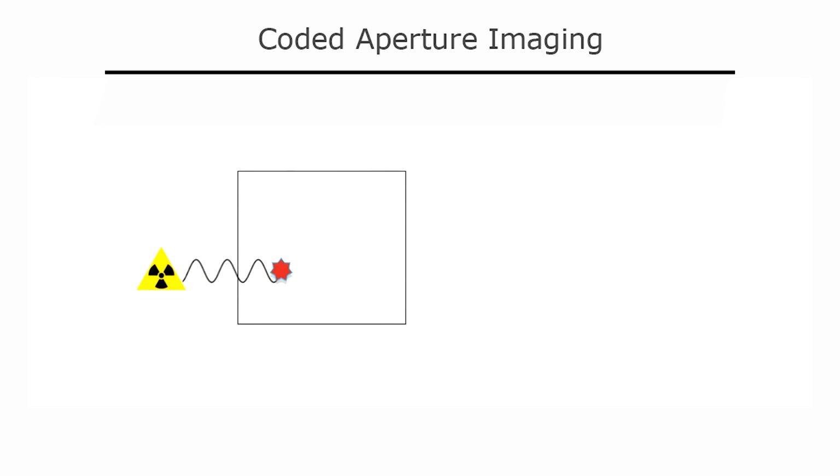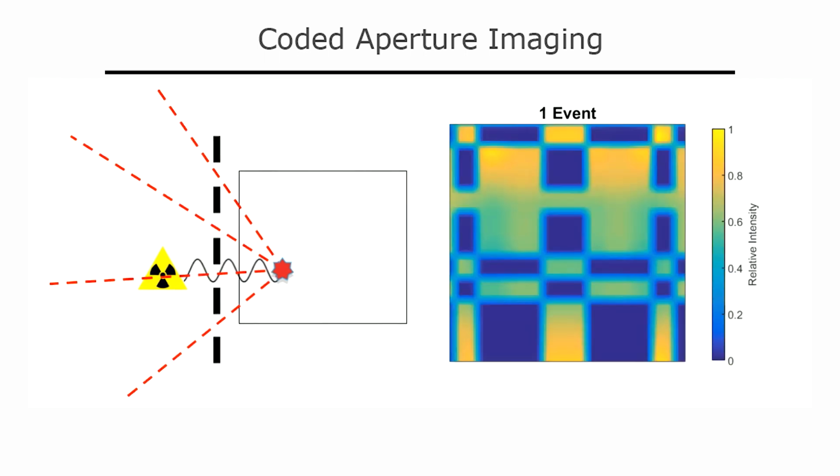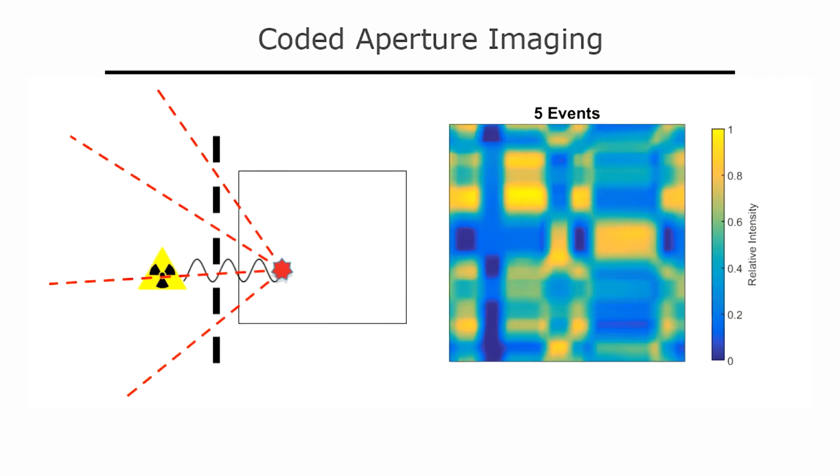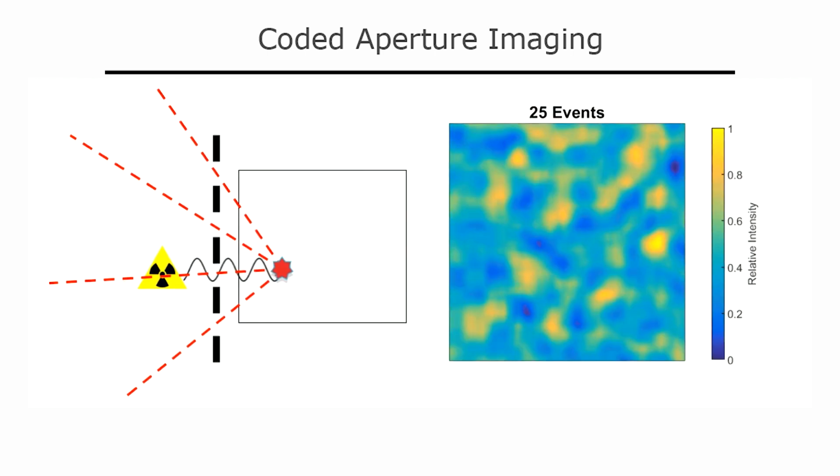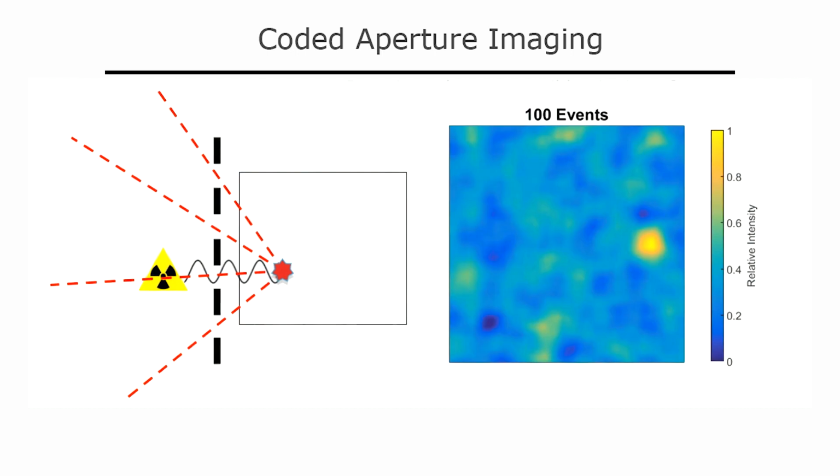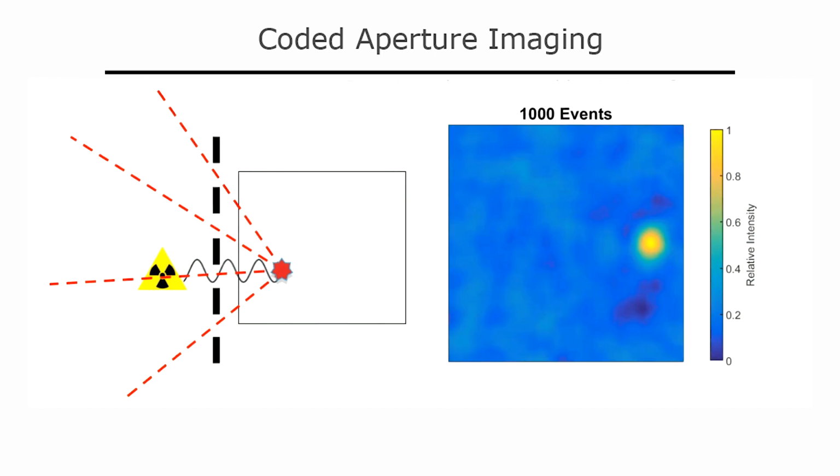Inside compatible H3D systems, thin pieces of tungsten form a patterned mask that sits between the source and detector, blocking low-energy gamma rays. When gamma rays interact with the CZT, potential gamma ray source locations are projected back through the gaps in the mask. Similar to Compton imaging, as more gamma rays interact, the potential locations of the source will eventually converge. This coded aperture gamma ray image can be overlaid on an optical image to show the location of the source in the real world.